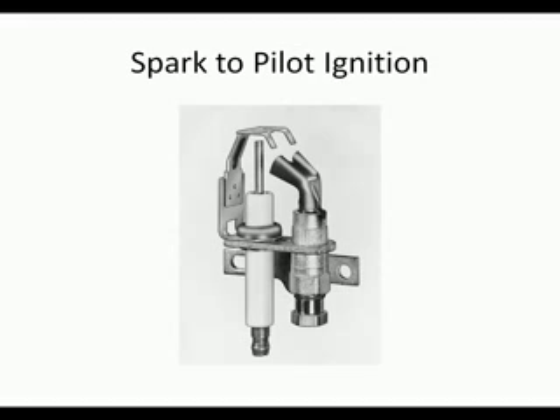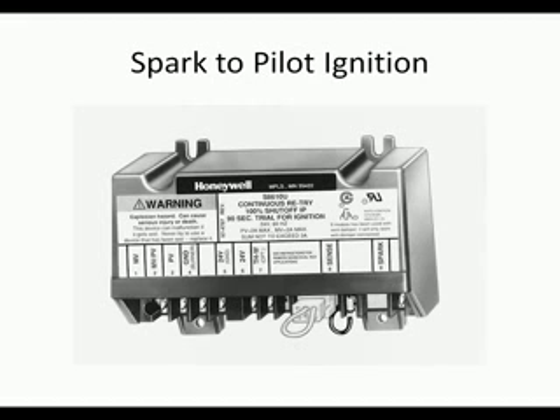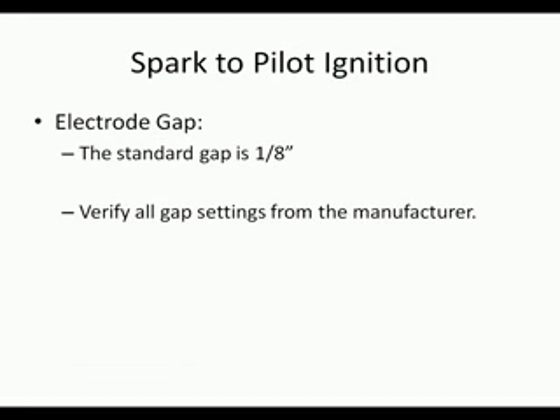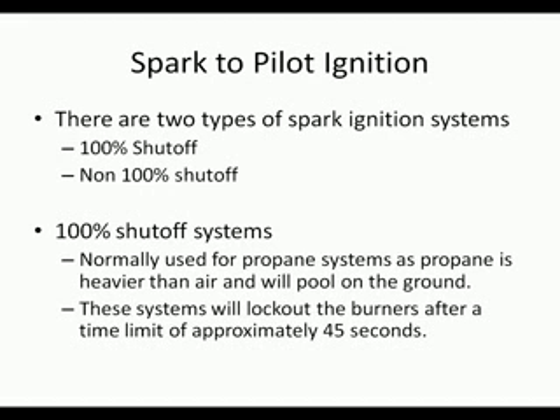Required parts of this system: you have to have the electrode sealed in a ceramic insulator. Any cracks in this insulator will allow current to flow to ground and cause a weak spark. You have to have a high voltage lead wire connecting the ignition control and the electrode. This is the spark-to-pilot ignition sensor and how it mounts into the pilot burner. The spark goes from the top of the igniter onto the band above it. You also have to have a pilot spark ignition module. This is the Honeywell module, and all the connections are labeled on it. Very important, you must have a good ground from your burner. The electrode gap setting is 1/8 of an inch, but you want to verify all these gap settings with the manufacturer's instructions.